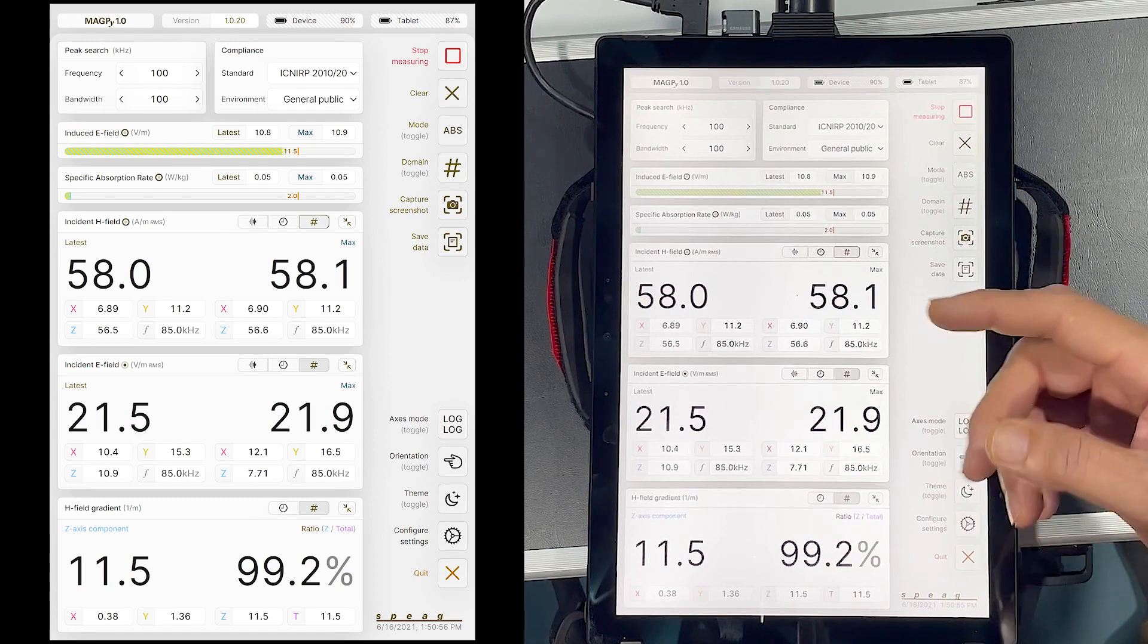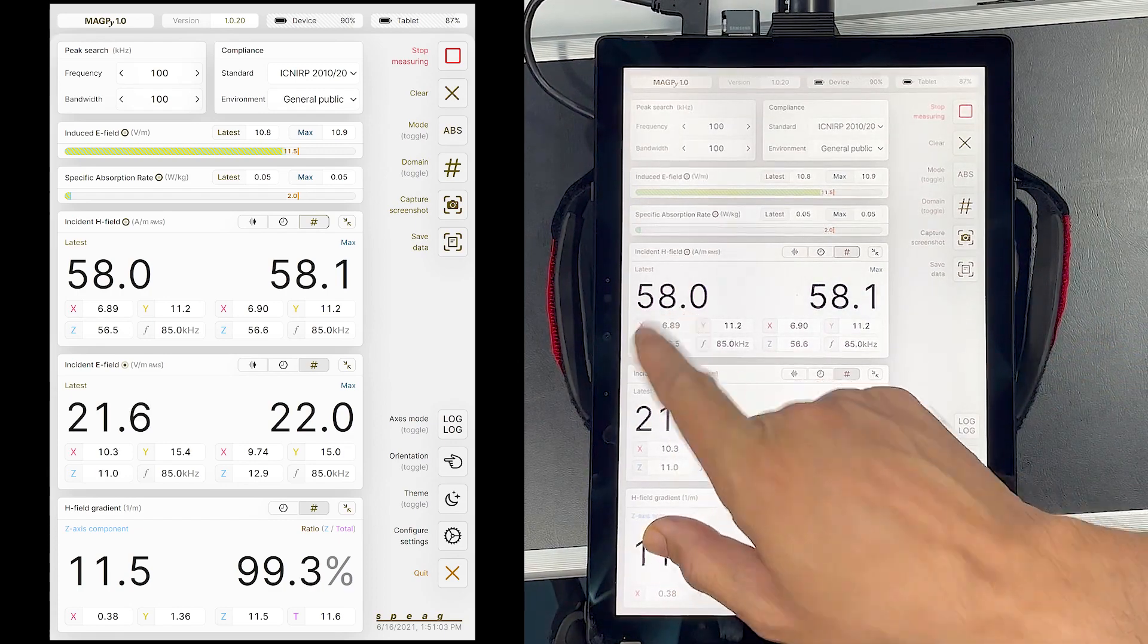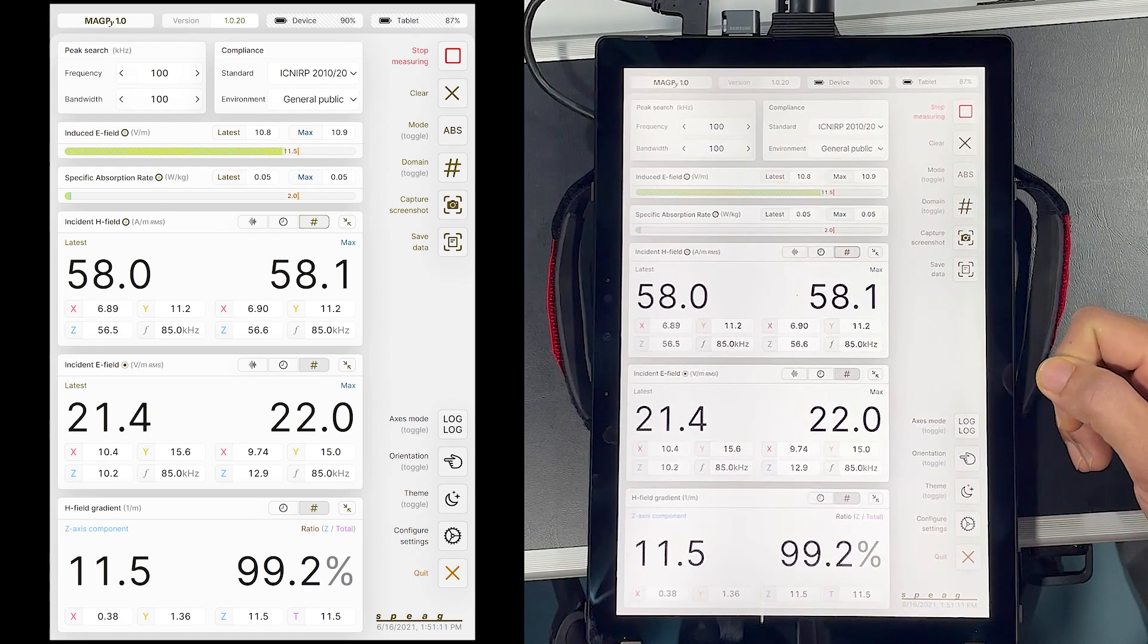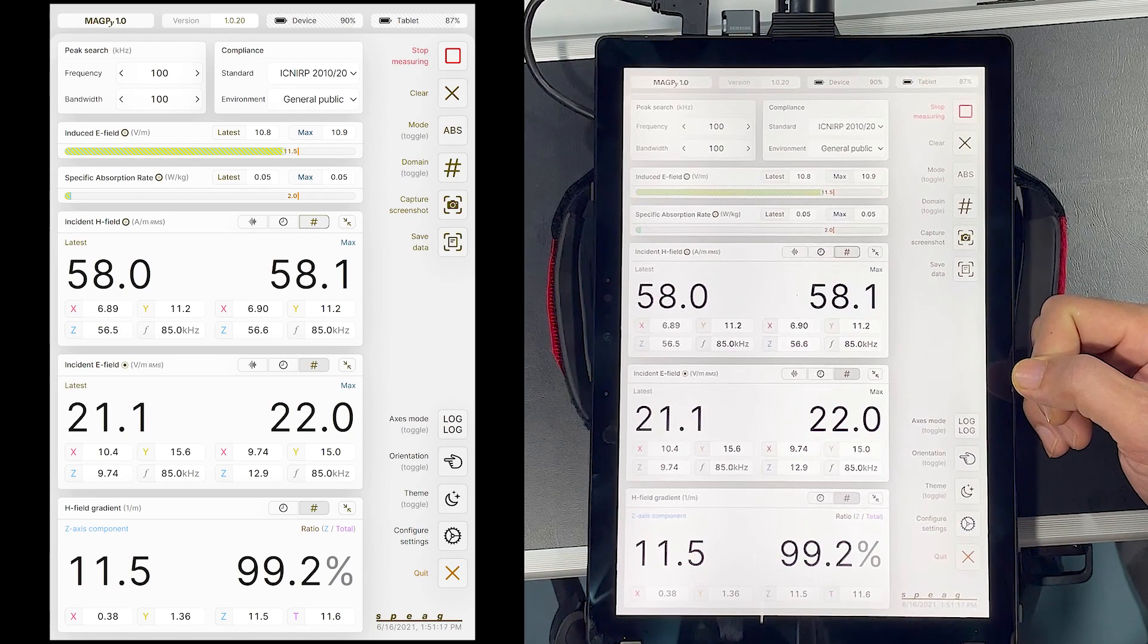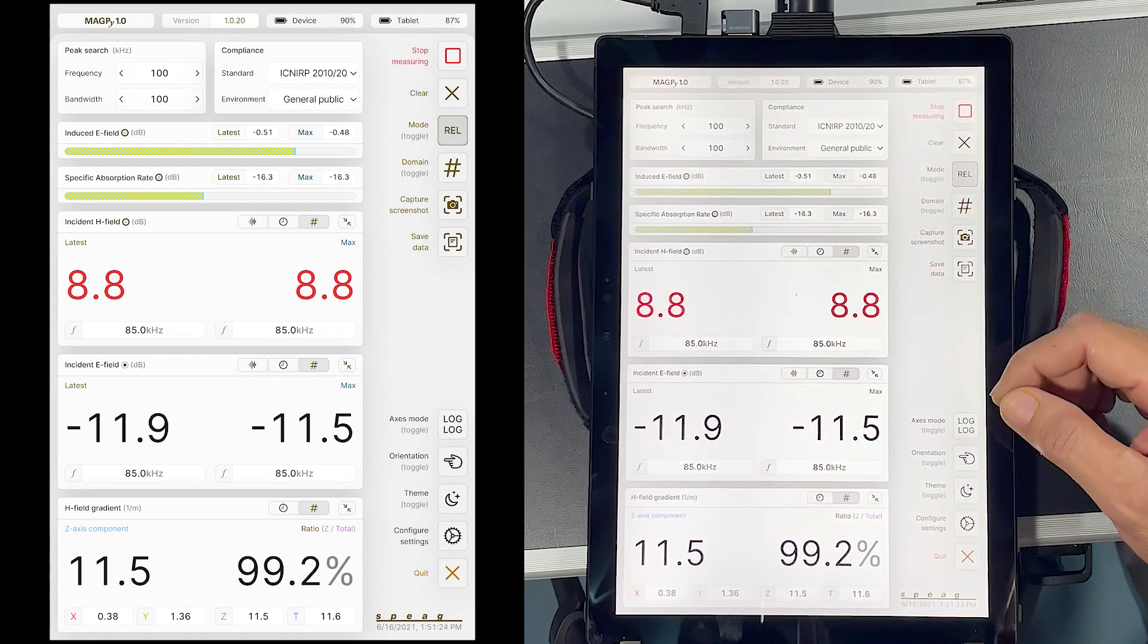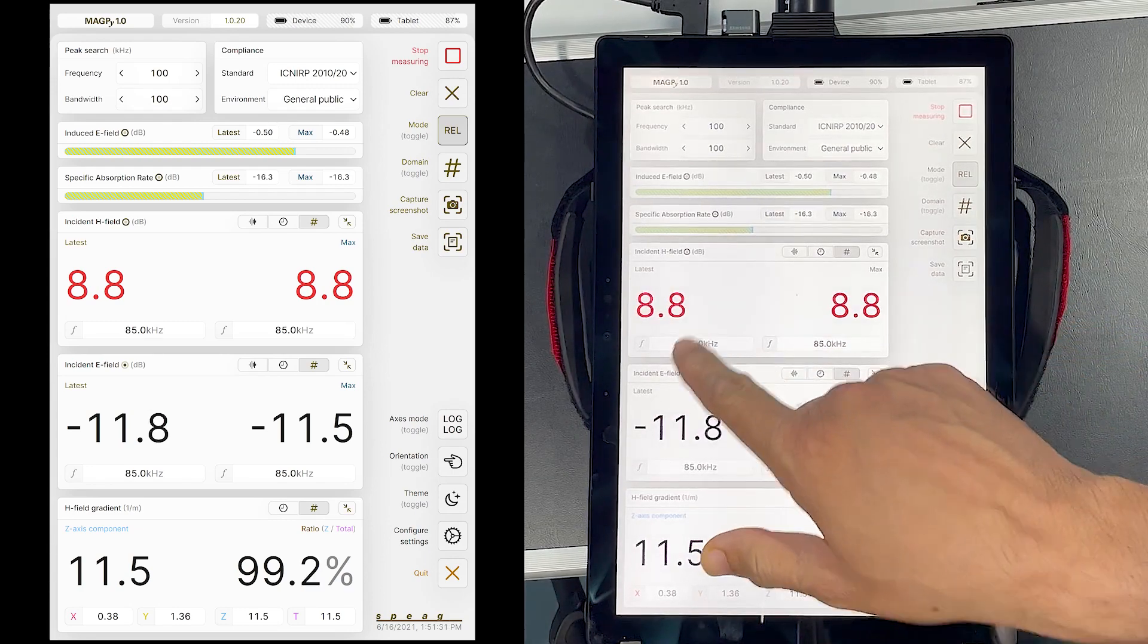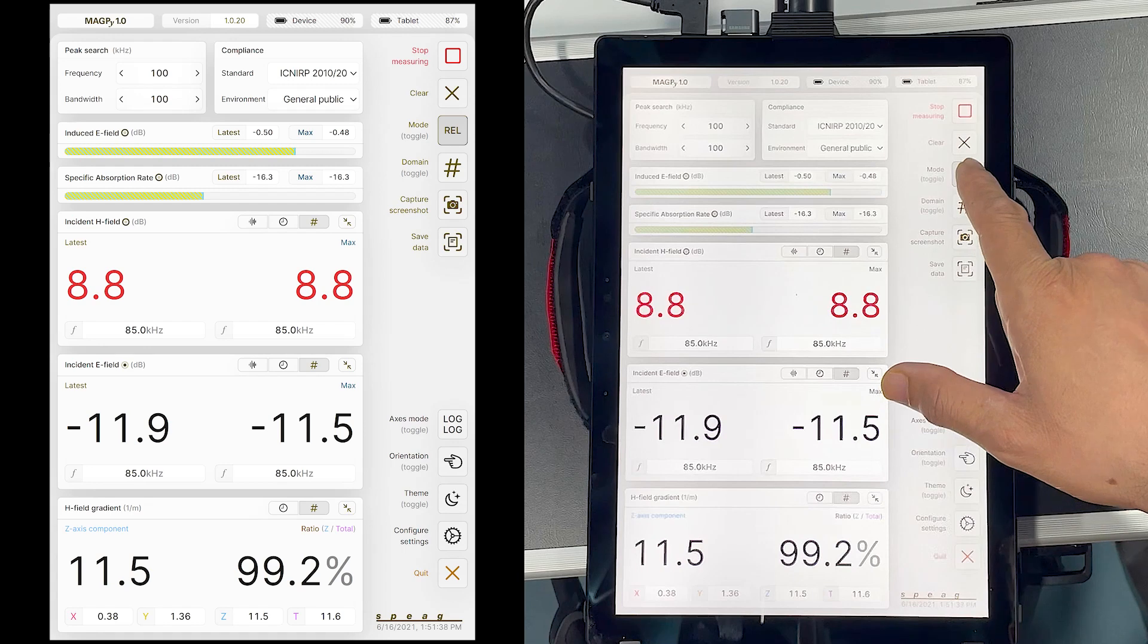The total magnetic field at this point is already relatively high. 58 amperes per meter at 85 kHz. While the ICNIRP limit for the incident magnetic field at 85 kHz is 21 ampere per meter. The field is thus a factor of approximately 9 dB above the limits. If I switch to relative mode, it shows the ratio of measured field and limit as 8.8 dB.